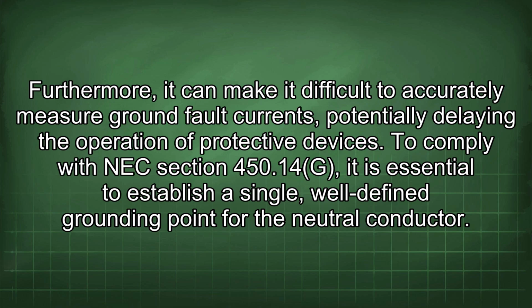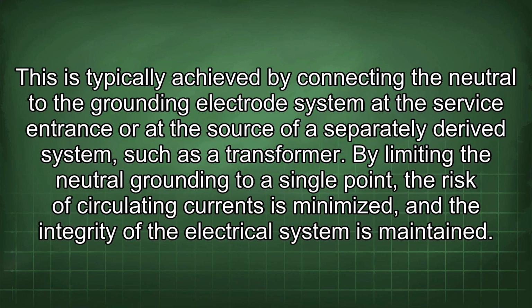To comply with NEC Section 450.14g, it is essential to establish a single, well-defined grounding point for the neutral conductor. This is typically achieved by connecting the neutral to the grounding electrode system at the service entrance or at the source of a separately derived system, such as a transformer. By limiting the neutral grounding to a single point, the risk of circulating currents is minimized and the integrity of the electrical system is maintained.